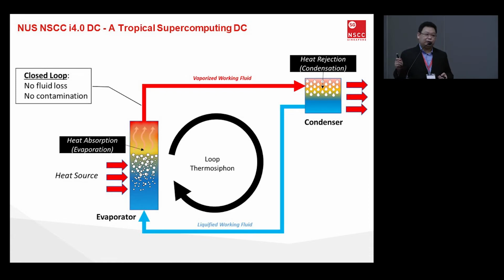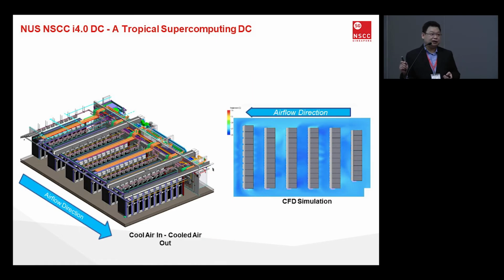As I mentioned, we kept it at 26 degrees because we did a CFD, and this is the best temperature to run the system. This design is also a bit different from most data centers. Most data centers use a front-back system so that they can do aisle containment, but in this particular case, we don't. The cold air comes in from the front, goes into the racks, gets heated up, comes out into the shared cooling chamber, and gets cooled by the rear door. By the time it comes out, it's aircon temperature, about 24 to 26 degrees.